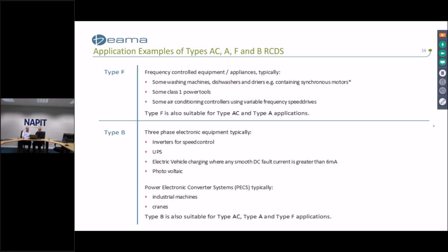A typical use for a Type B RCD is for electric vehicle charging, particularly where DC fault currents greater than 6 milliamps can occur. It must be noted that these are examples, and appliance manufacturers' instructions must be considered when selecting the appropriate type of RCD.